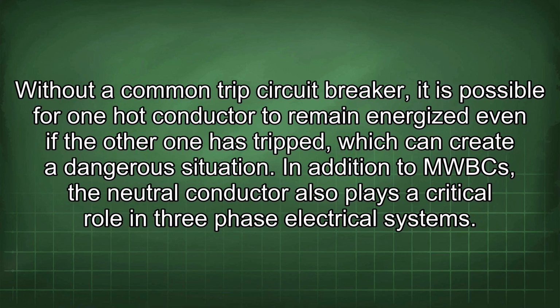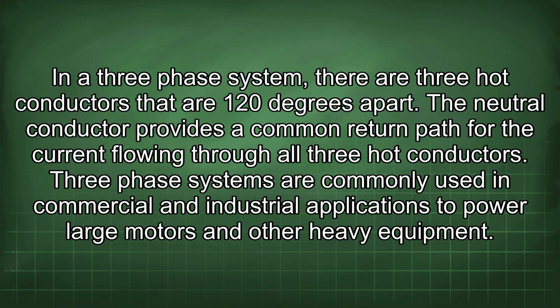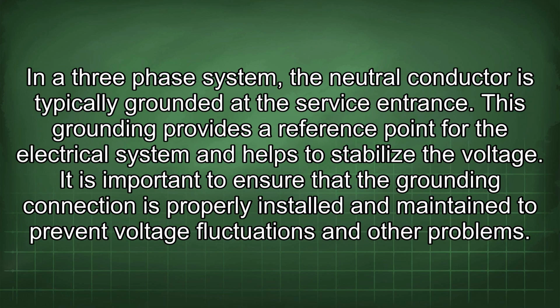In addition to MWBCs, the neutral conductor also plays a critical role in three-phase electrical systems. In a three-phase system, there are three hot conductors that are 120 degrees apart. The neutral conductor provides a common return path for the current flowing through all three hot conductors. Three-phase systems are commonly used in commercial and industrial applications to power large motors and other heavy equipment. In a three-phase system, the neutral conductor is typically grounded at the service entrance. This grounding provides a reference point for the electrical system and helps to stabilize the voltage.